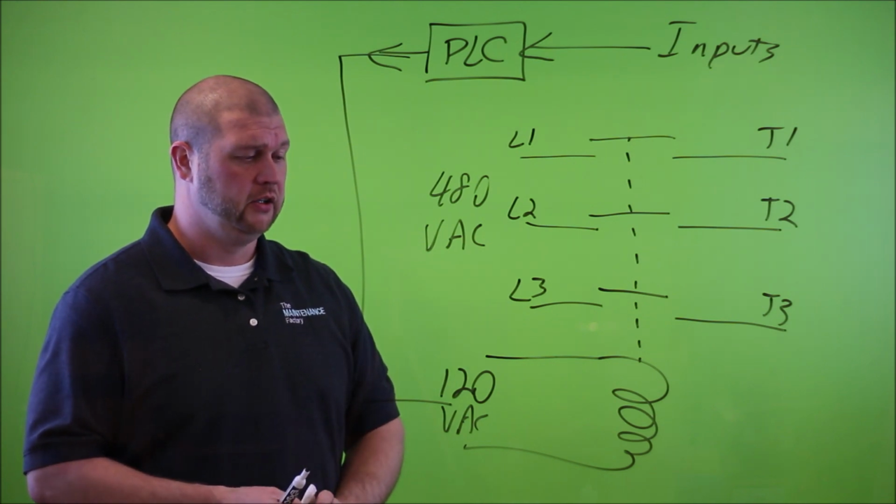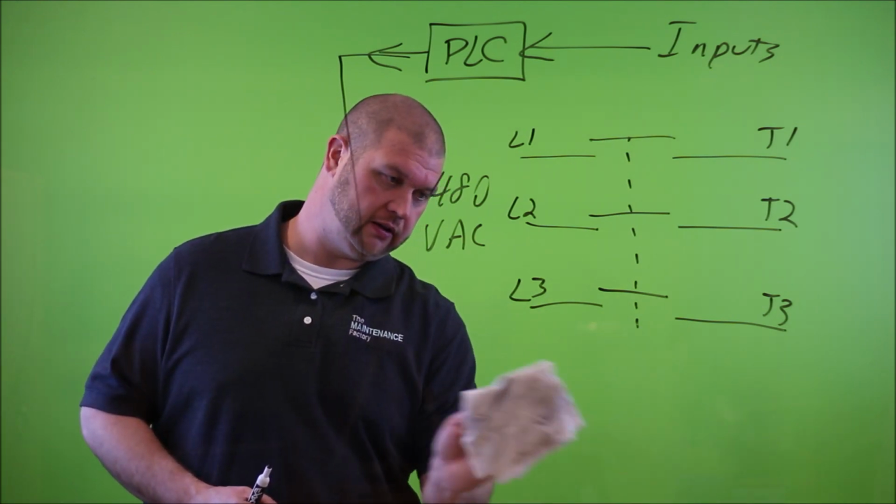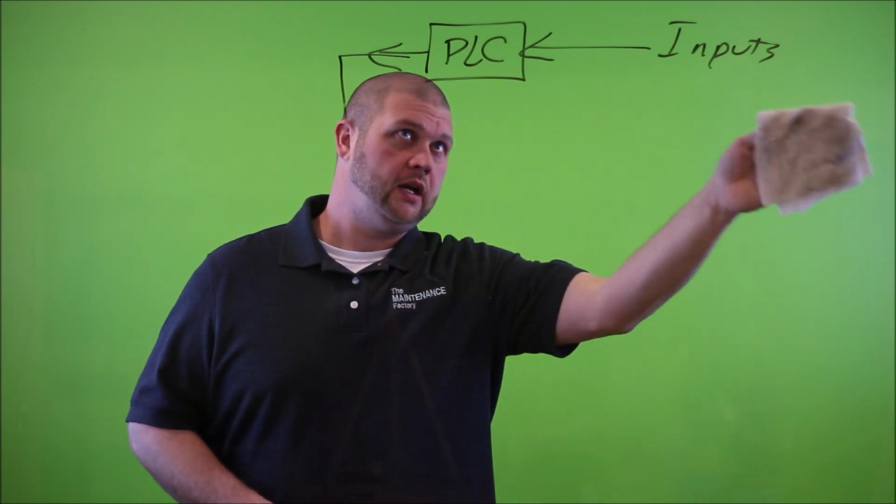So go back to the example of the knife disconnect. Let's say, for example, we have a 200 horsepower air compressor, and the only means of starting it is a disconnect. Well, we can go close the disconnect and the motor starts to run. A 200 horsepower motor can use up to 240 amps at full load. And to put that into perspective, a common household in America today has a 200 amp service panel in the house. So it would require more power to operate this 200 horsepower motor than what would be supplied in an everyday household.